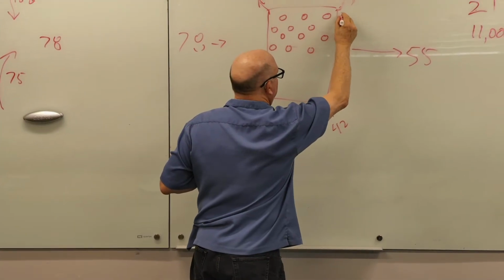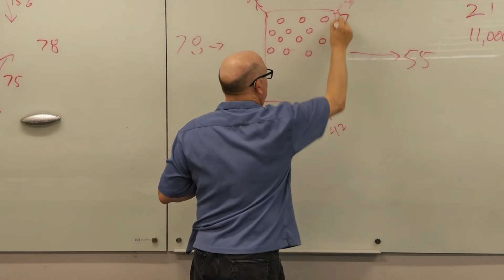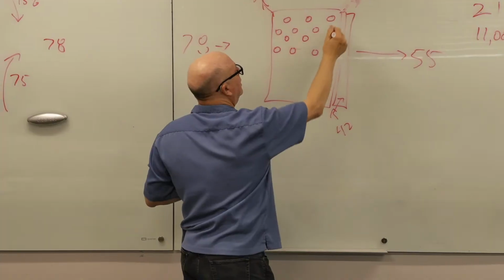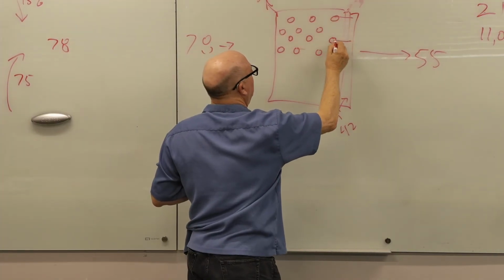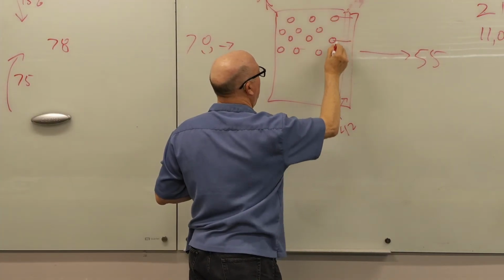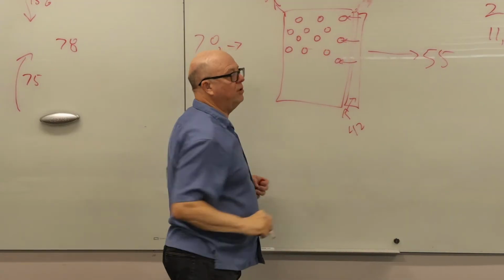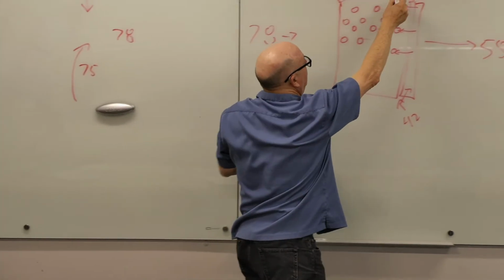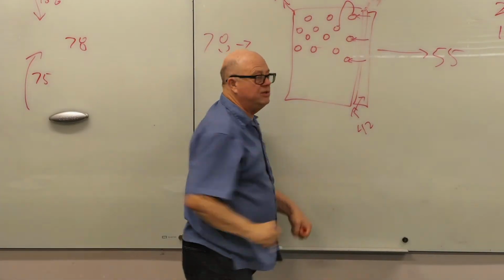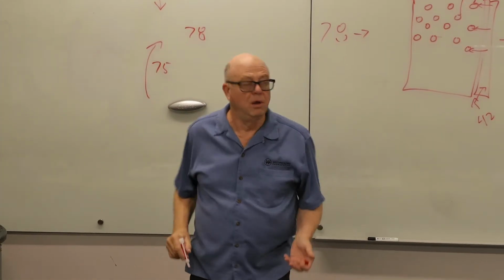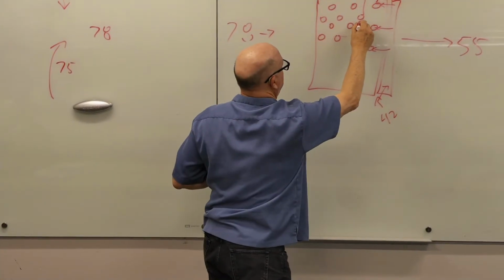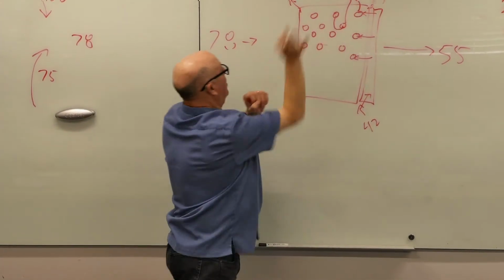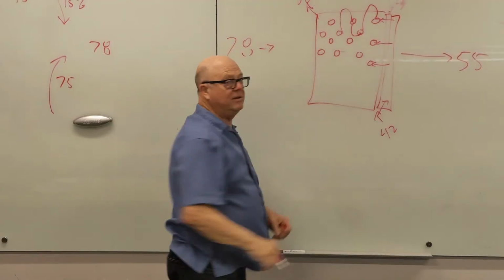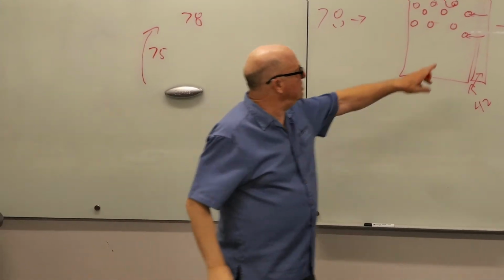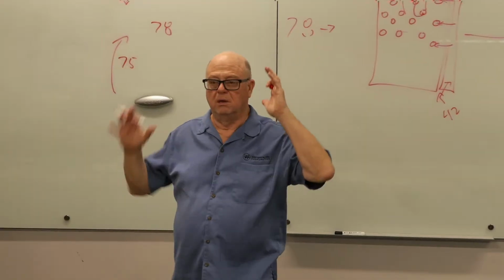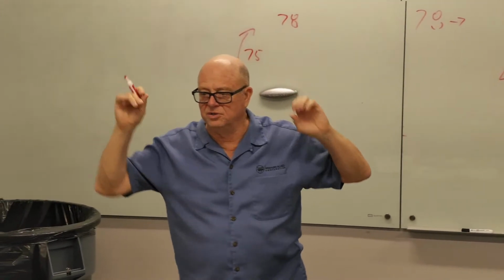Now we've got a header here, and the water's going in the header. If you're feeding every coil in the front row with water, or every tube in the front row with water, and then on the back side, there's a U that does that and flips it around to the next row, and then on this side there's a U that does that, and on the back side it does that, so that we go through. Okay, that's a full circuit because the whole full face of the coil is getting water.